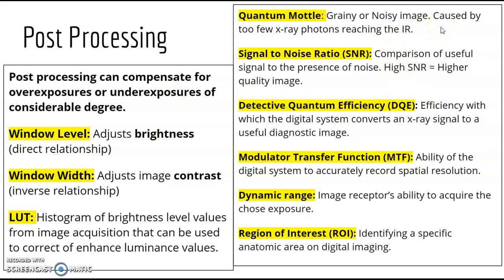Quantum mottle is when the image looks grainy or noisy — too few x-ray photons have reached the image receptor. Signal to noise ratio: you always want a high SNR, meaning less noise and more signal. Signal means x-ray, so you want more actual x-ray versus noise on your image for a higher quality result.